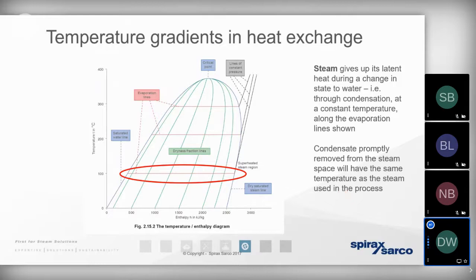So the energy that's left behind, once that latent heat energy has entered the process, is the sensible heat. That's demonstrated in the enthalpy of water, the first column on the steam tables. And that's about 25% of the total heat energy present within that mass of steam. So there's nowhere near enough energy present within the condensate to heat the process. We need to get it away. But the one area where we can use that energy in the condensate to good effect is by returning or recovering it back to the boiler house again.